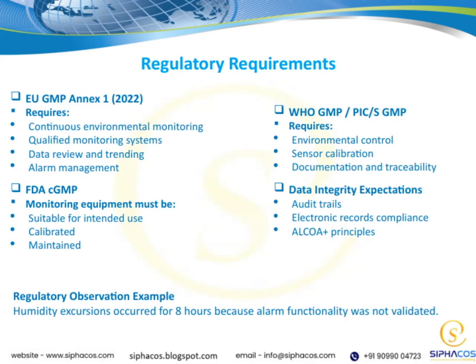Let's talk about regulatory requirements, a critical piece of the puzzle in any controlled environment. For example, humidity excursions lasting hours can happen if alarm systems aren't properly validated. Guidelines like WHO GMP and PIC/S GMP demand strict environmental control, sensor calibration, and thorough documentation. Meanwhile, data integrity is front and center, with audit trails and ALCOA plus principles ensuring records are trustworthy. The latest EU GMP Annex 1 calls for continuous monitoring, qualified systems, and proactive alarm management. And the FDA requires that all monitoring equipment be suitable, calibrated, and well-maintained.